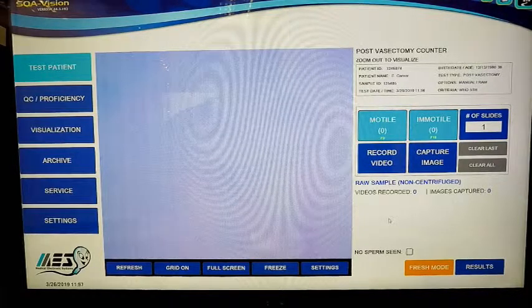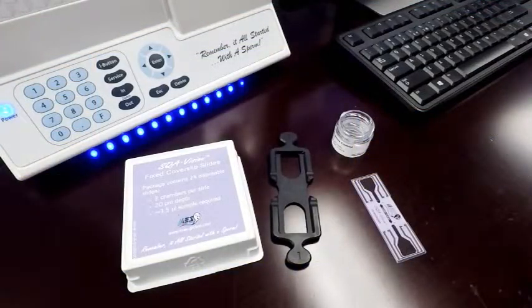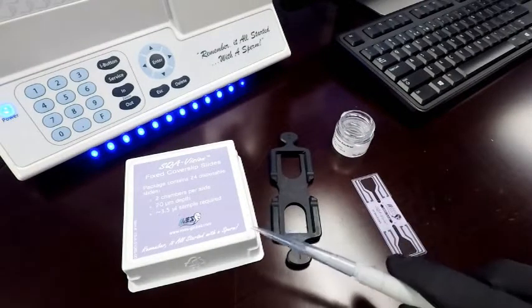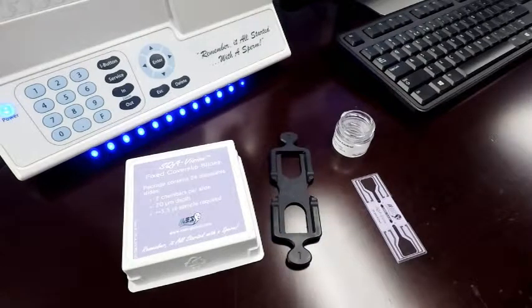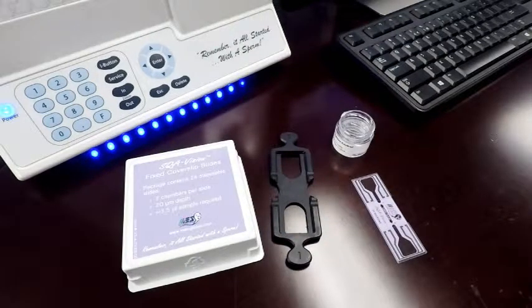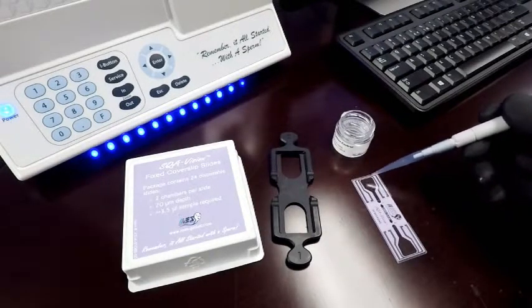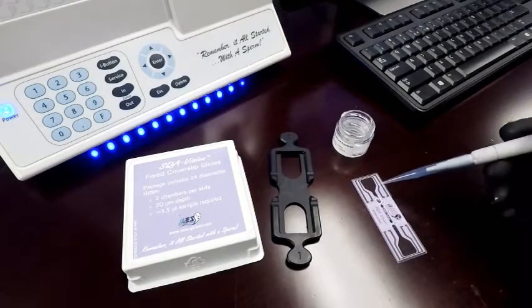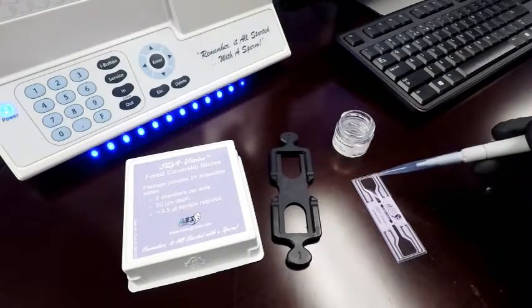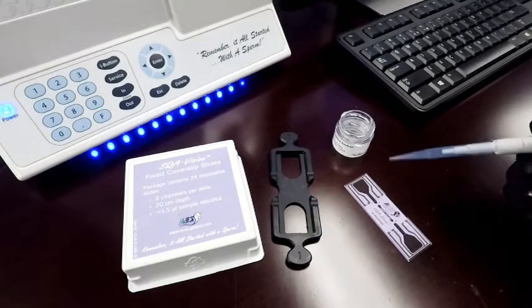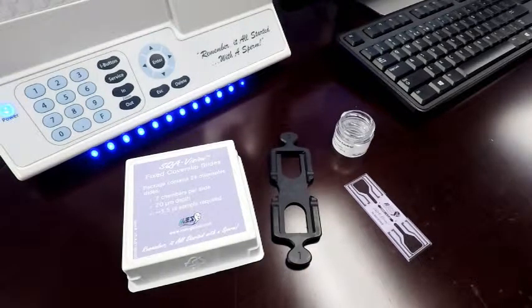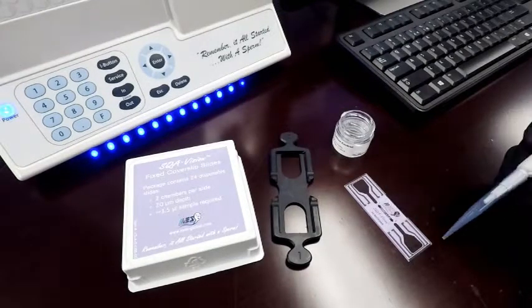Let me show you how to prepare our slide. Here are the supplies we're going to use. We've got a fixed coverslip slide that Medical Electronics Systems manufactures. You can also use a standard 1 inch by 3 inch lab slide with a 22 by 22 coverslip. That'll achieve the same 20 micron depth that our fixed coverslip slide has naturally. Fixed coverslip slides are nice because you don't have to worry about spillage or the floating nature of the coverslip. It's just fixed, you can't overfill it. It's easier to use but both offer a perfect solution depending on budgets and if you want to keep it standardized.